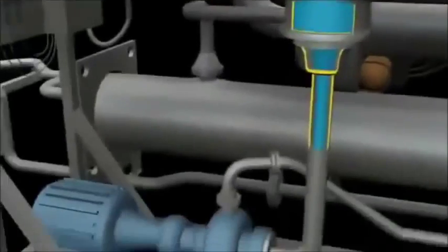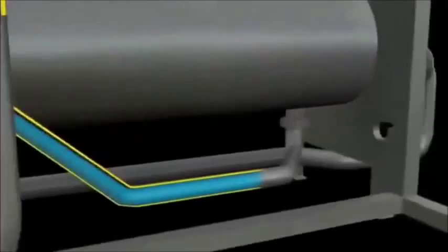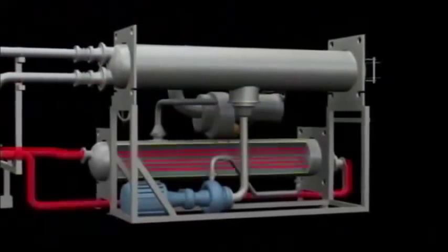The working fluid now flows down the tank outlet to the pump, where it is re-pressurized and injected back into the heat exchange tank to repeat the process. It is important to note that the three fluid systems of hot well water, cooling water from the cooling tower, and system working fluid remain in their own separate loops.